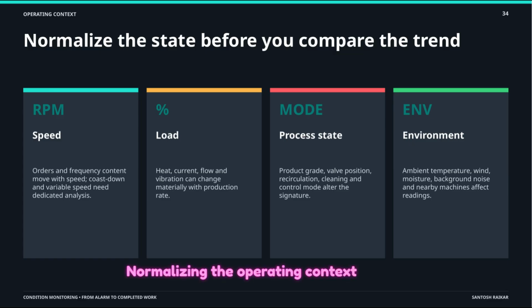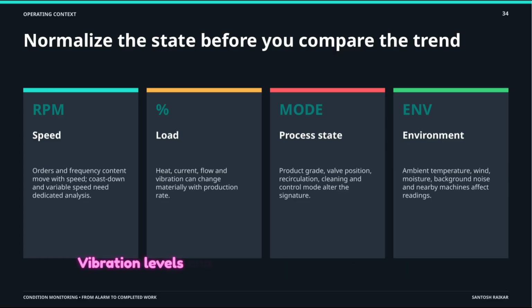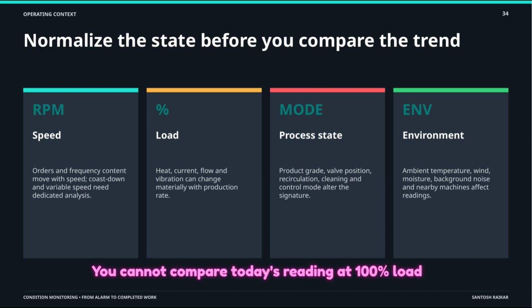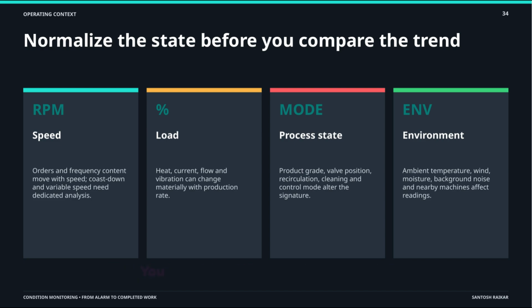Normalizing the operating context is vital. Vibration levels and temperatures will naturally change with RPM, load, and even the ambient environment. You cannot compare today's reading at 100% load to last month's reading at 50% load and call it a trend. You have to compare apples to apples.